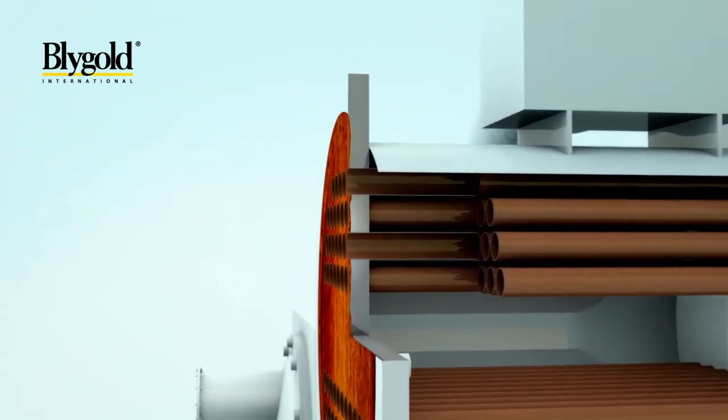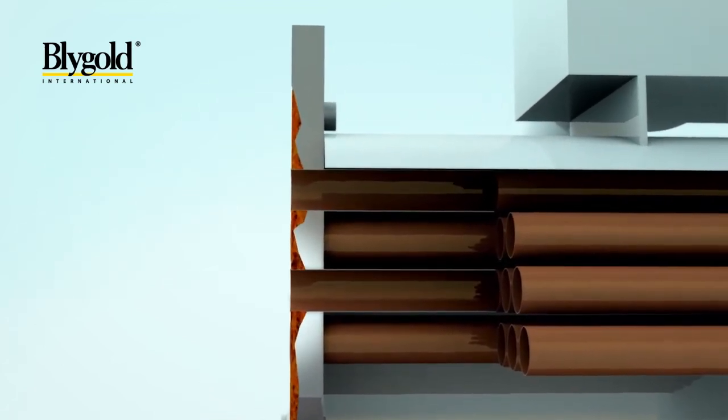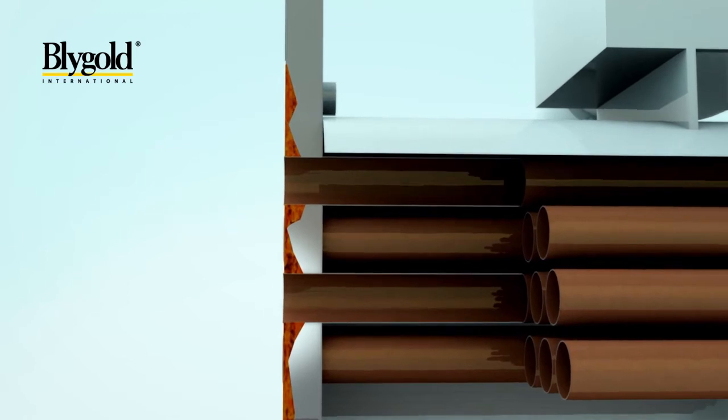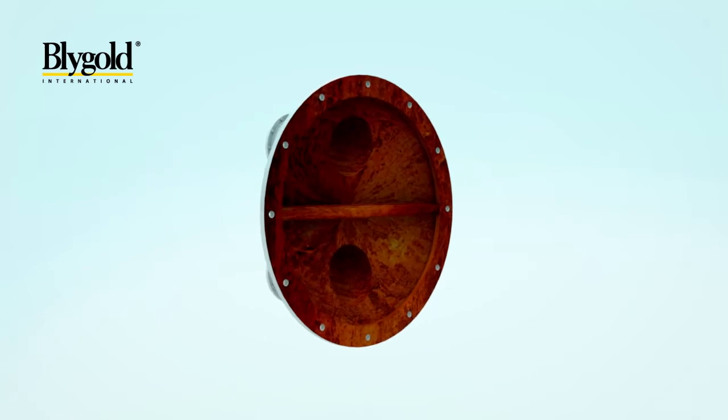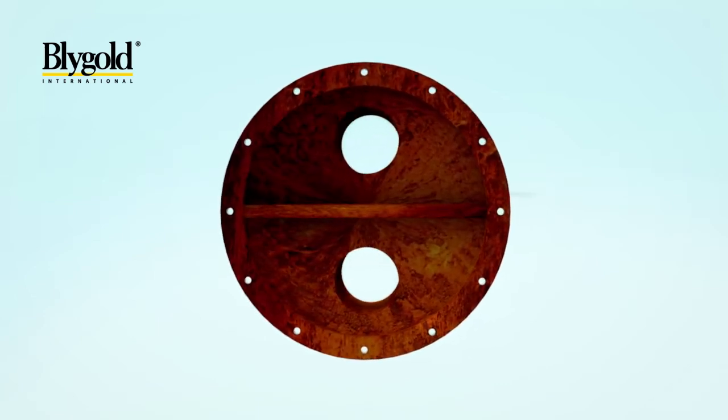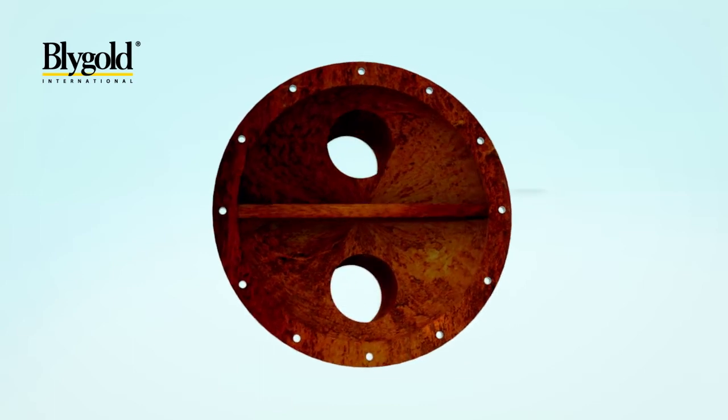Due to this galvanic action, the tube sheet loses thickness rapidly and, as a result of that, the capability to resist the high-pressure gas in the shell of the heat exchanger. Next to the galvanic corrosion around the tubes, the overall surface of the tube sheet, water box and covers is affected significantly.